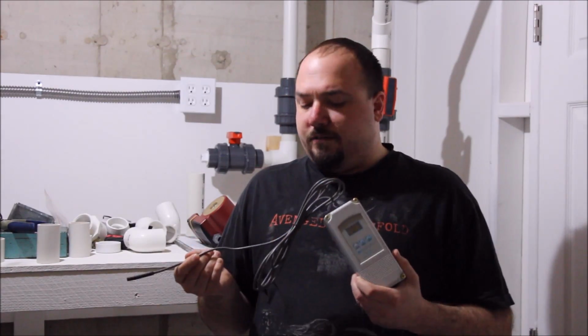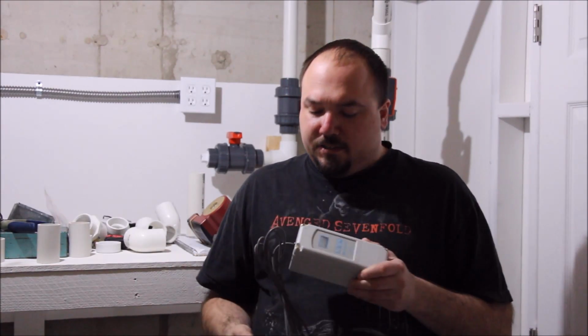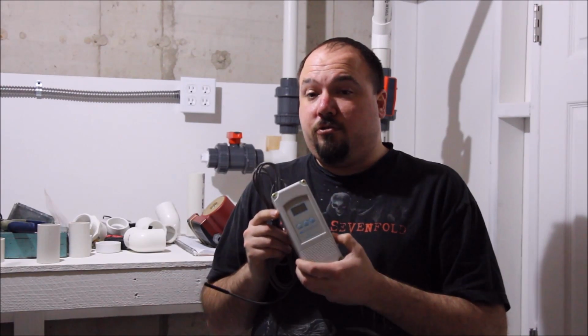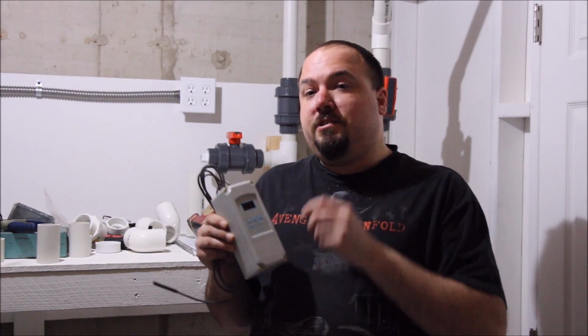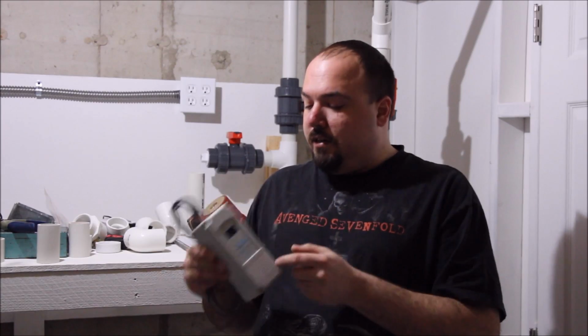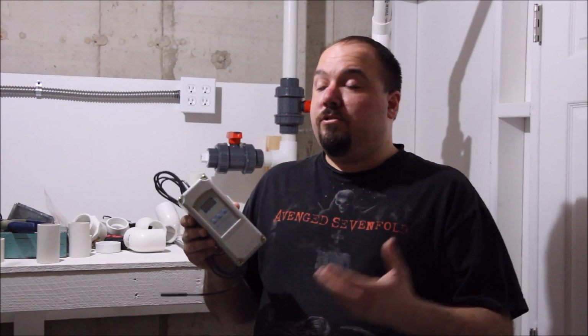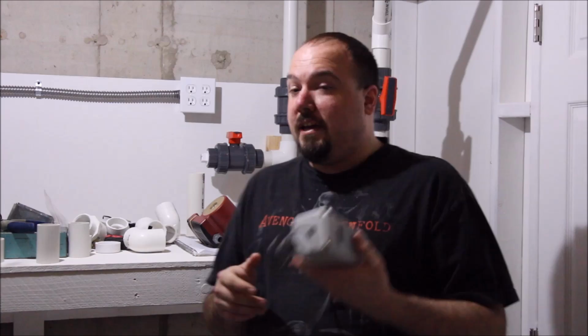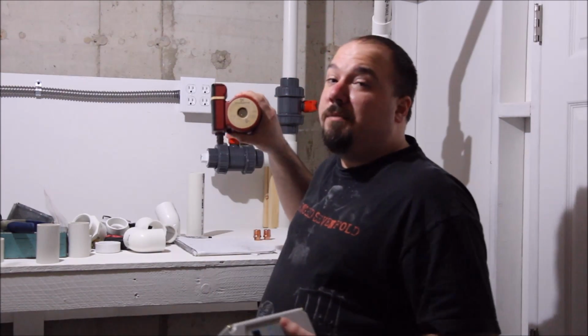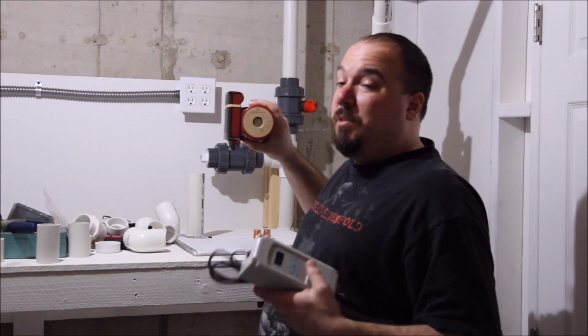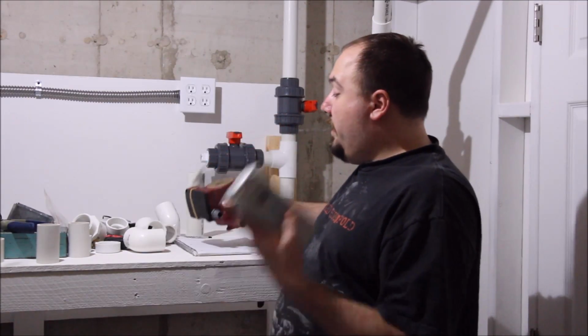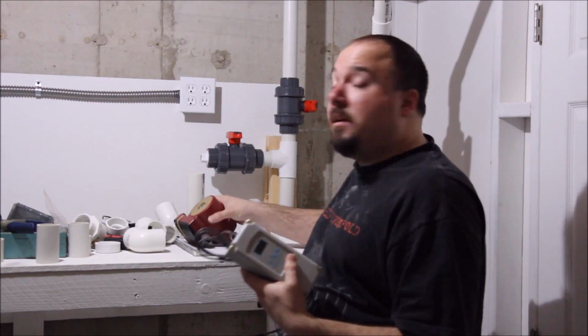The Ranco single stage controller is similar to just about any aquarium controller like an Apex—it's essentially an industrial temperature controller. You set your temperature in here, and it'll energize something to make it work. In this case, the recirculation pump will start kicking on and pumping hot water in when this makes a call saying the temperature's too low.